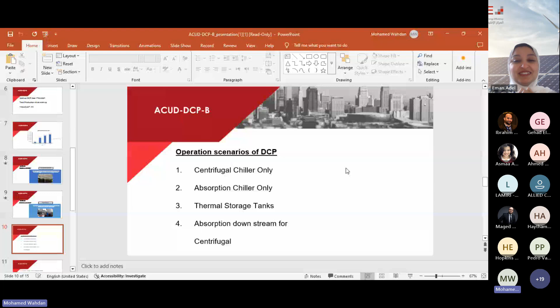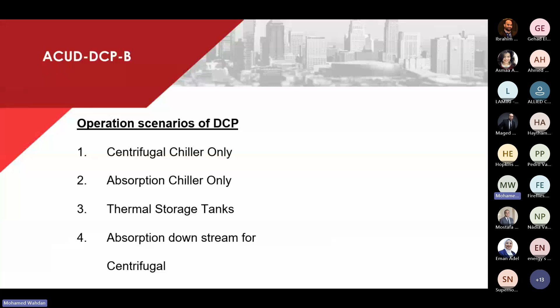Operation scenarios for DCP: we can use centrifugal chillers only, or absorption chillers only, or thermal storage tank, or a combination of the centrifugal chiller and absorption chiller, or a combination of the absorption chiller and thermal storage tank, or a combination of all of them. We can use the thermal storage tank at night, and produce chilled water from the absorption chiller or centrifugal chillers according to the electricity tariff or what is available at the time, then store the chilled water and use it throughout the daytime.